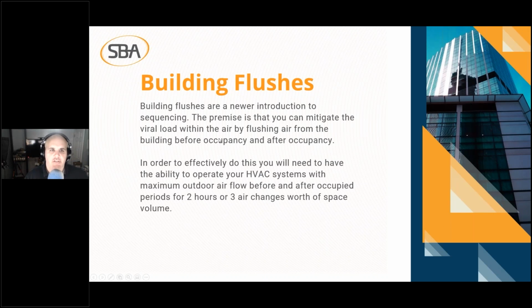And finally, building flushes. This is the next big thing, which is building flushes are a newer introduction to sequencing. If you've ever done a LEED project and you've done that 24-hour flush to get rid of the VOCs from new carpet and new flooring that LEED requires, then this should be somewhat similar to you. Basically, the premise is that you can mitigate the viral load within the air by flushing air from the building before occupancy and after occupancy. Now, in the standard, or in the recommendation, it says, first off, you need to do this for about 2 hours before and after occupancy, or 3 air changes worth of space volume.